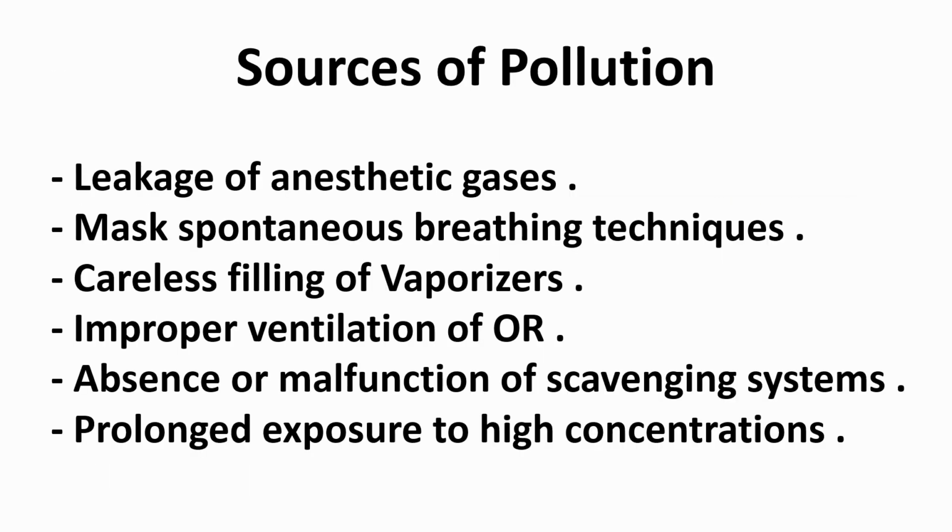So, what are the sources of this pollution inside the OT or inside the operating room? Maybe leakage of anesthesia gas during filling, due to a crack in the lines.